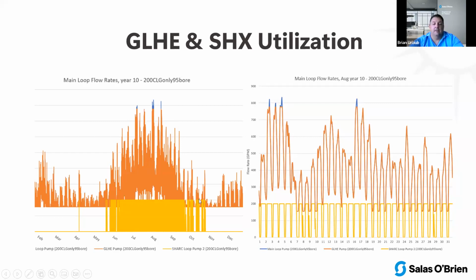So you can see here that, which was really surprising, we're really not utilizing it in the wintertime. Now you could turn it on more in the winter and turn your ground loop down, which is some of your controlled dispatches. But what you really needed it for was for cooling. We need to be able to reject heat to the sewer as well as the ground loop in order to reduce any bores. And so we went from about 128 bores on this site to 95 bores by utilizing the sewage heat recovery system.